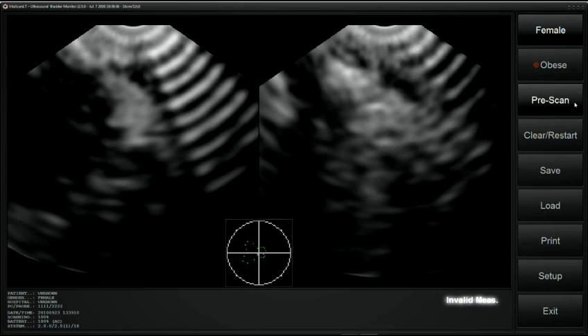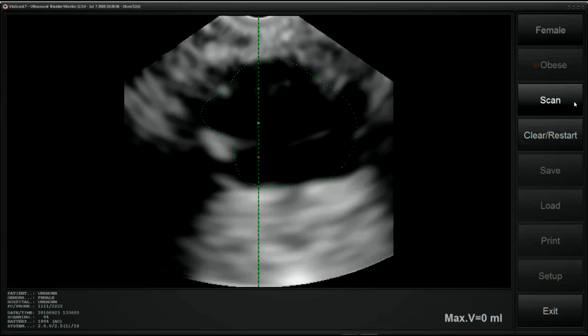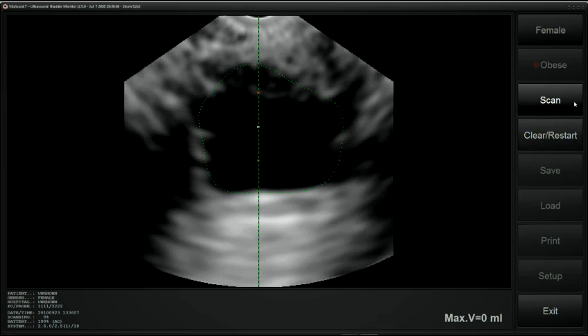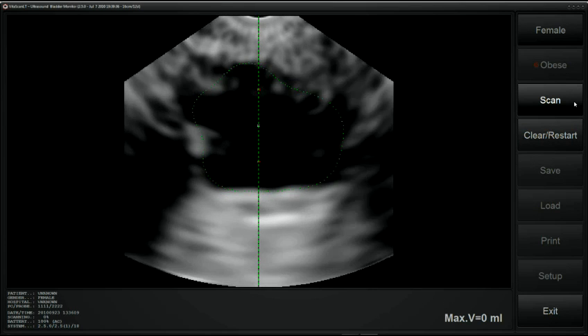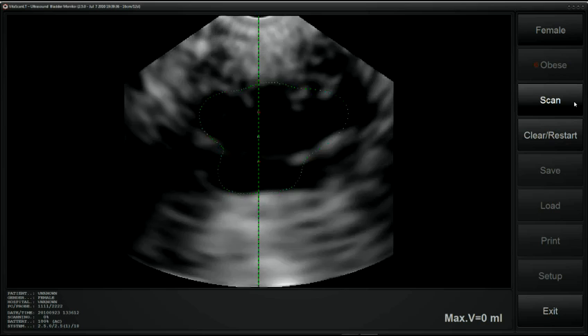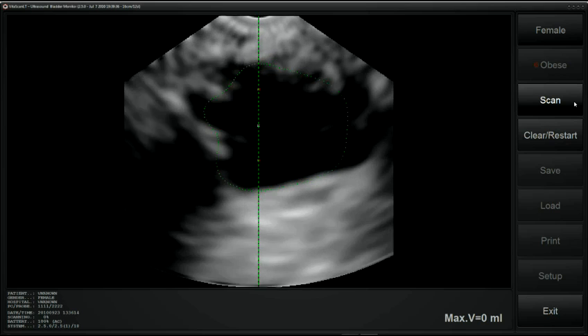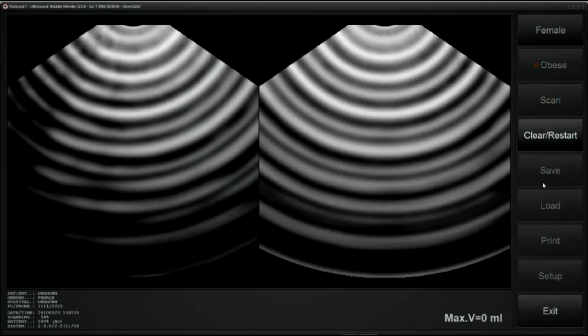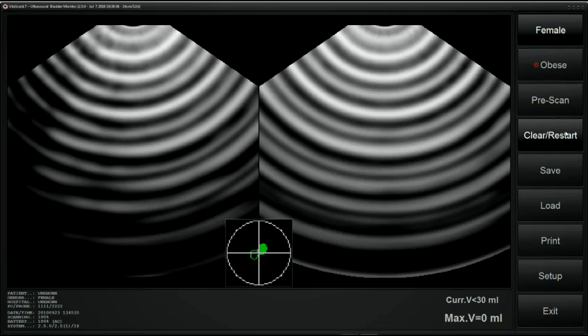InvMeasure equals invalid measurement. Press Pre-Scan and re-aim. Ensure that the whole bladder is captured inside the sector and that the bladder is in the center. Volume below 30 milliliters will not be recorded, and this message will be displayed.